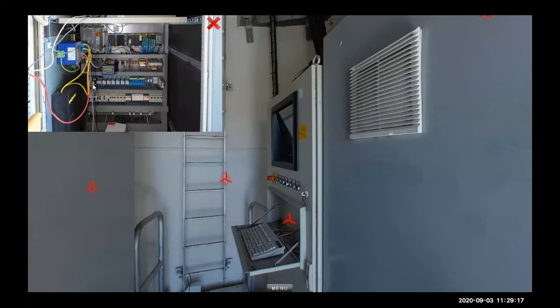And so you have also these relays here, and these are either 24 volt or 120 volt. This one you can't probably see, but it's orange, so it's a different voltage than these that are blue, but they're just a little box that you bring the wires in the top in and the wires in the bottom out, and they're a switch. So what happens is this PLC has solved some kind of logic, and then it sends its output through one of these relays that closes, and then that's going to turn something on.